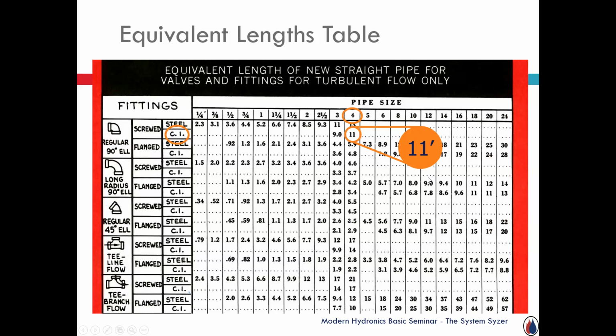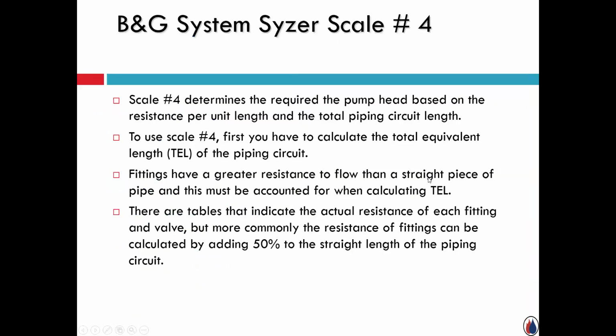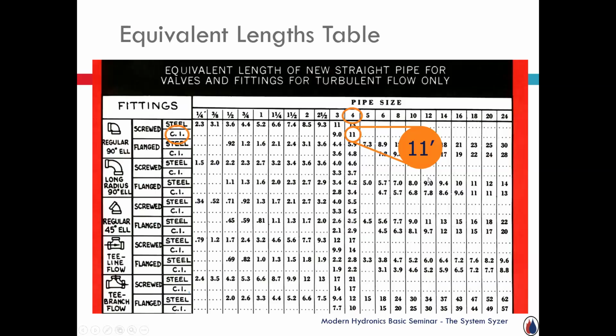With that ASHRAE K factor, is it doing the same thing, assigning a TEL for a fitting? Oh, okay. You're probably a little more accurate than this thing. Yes, I would say that's more accurate, absolutely. In a world where you're designing and specifying and creating the system, you're staying in that world. More accuracy. This is back to what they would reference in the industry as a rule of thumb, that 50% factor. The chart's a little more accurate than that because manufacturers tested it, but I'm thinking that K factor is probably even a little more fine-tuned than what this was from years back.